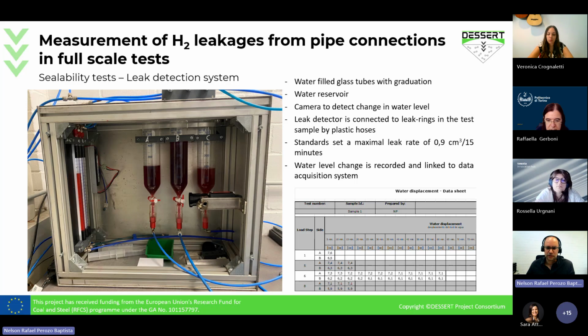If this value is changing with numbers above the leak rate, then we need to extend the hold step until the pressure is stabilizing and this change of the leak rate is also stabilizing. Otherwise, if this is not happening, we're having leakages in the connection.